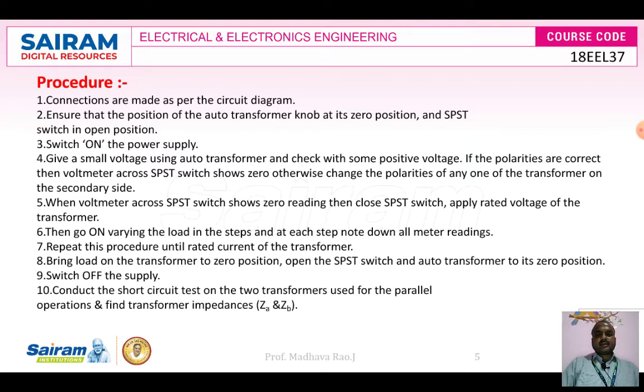If the polarities are correct, then the voltmeter across the SPST switch shows 0. Otherwise, change the polarities of any one transformer on the secondary side. If the voltmeter across the SPST switch shows any voltage, we have to interchange any secondary terminal of the transformers. When the voltmeter across the SPST switch shows 0 reading, close the SPST switch and apply the rated voltage of the transformer. Then go on varying the load in steps, and at each step note down all meter readings. Repeat this procedure until the rated current of the transformer.